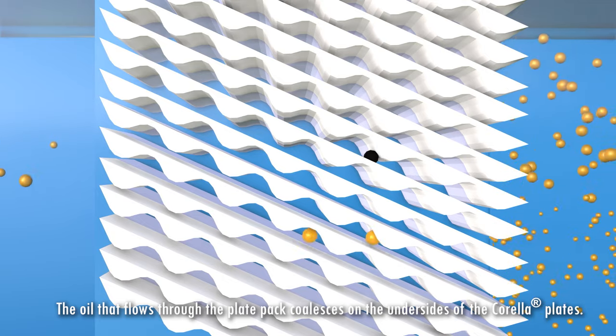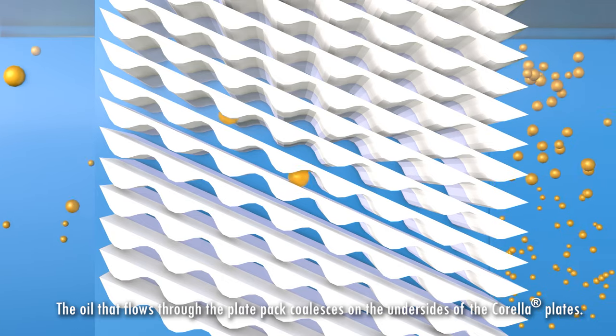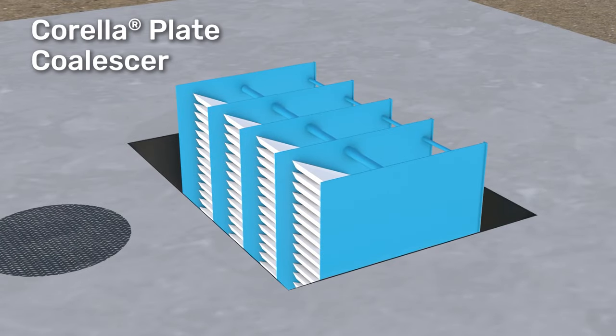Oil is moving through the corrugated plates and the corrugations are trapping the oil, forcing them to coalesce and form larger particles of oil. So they're being directed upwards to the top of the water.